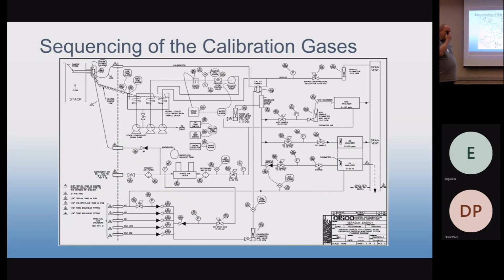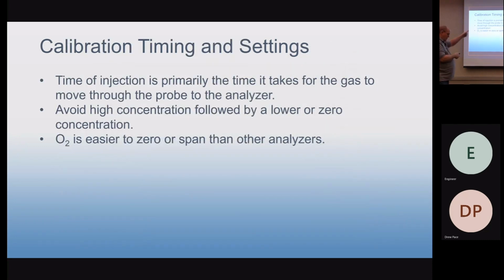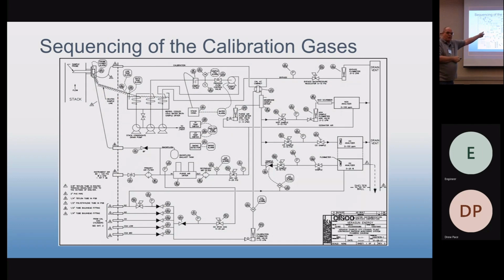Okay, the next thing I want to say, and both of these topics, I'm going to go ahead and show it here. Calibration timing and settings and the sequencing of the calibration gases. They kind of need to be talked about together. Because of the EPA rule regulations, you have to start your calibration gas as close to the tip of the probe as practical. For CiSCO's purposes, we inject it right here in the probe where the straw extension is attached to the probe. So that forces the calibration gas to come through the filter and down through any of the sample handling, and then gets to the analyzer.